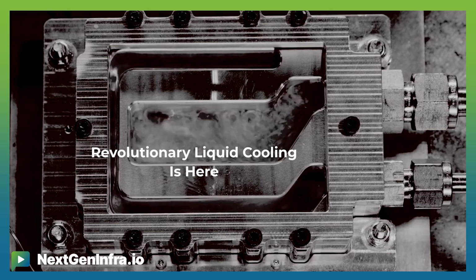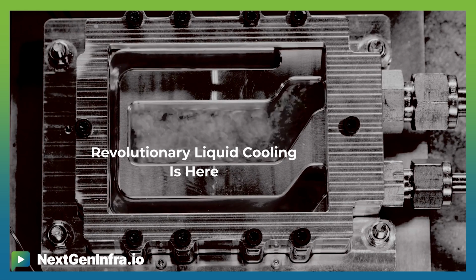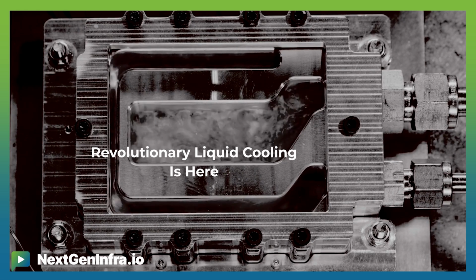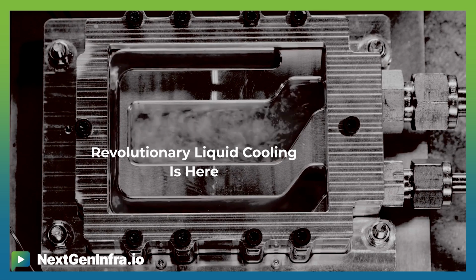When you bring single phase fluid over a chip, it starts cold and ends up warmer, usually about 10 degrees warmer from the start of the chip to the end. The chip experiences different thermal expansion and different thermal stresses because of that change in temperature. With two-phase cooling, our fluid doesn't heat up — it stays at the exact same boiling point. The only thing that happens is the liquid changes to vapor, and that's where the heat absorption is seen. That's a huge benefit to the chip, because now it's at the same temperature all across it. The thermal stress is near zero across that chip compared to single phase cooling.